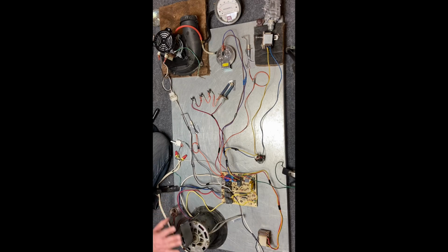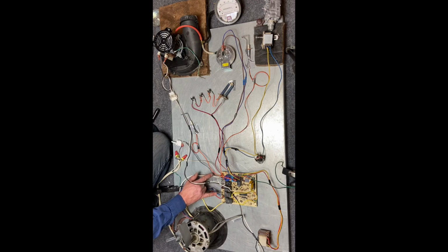Now the next thing I want to point out is our blower motor. What I've done is put tape on here so when it's running you can see this moving. And it's really going to be 2 wires at a time. There's a lot of wires, but it's 2 at a time. We see high speed and neutral, 2 wires, or I can use the heating terminal, the heating speed, which in this case is probably a medium low, to neutral.